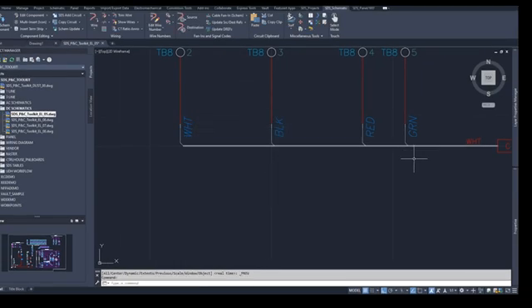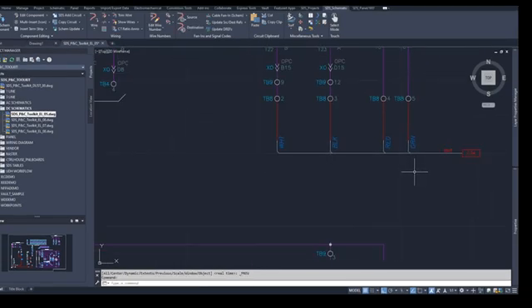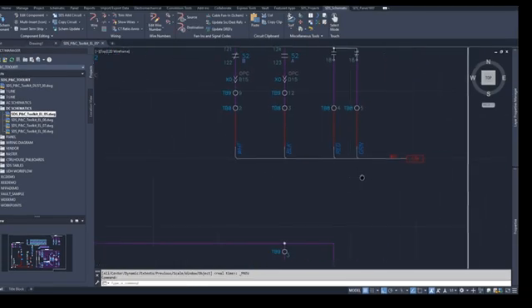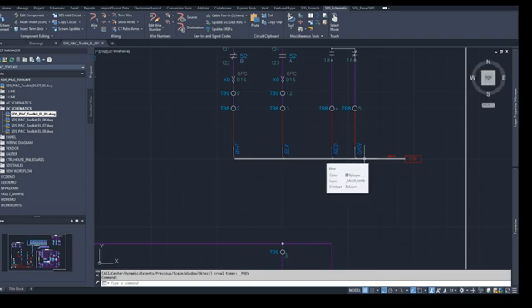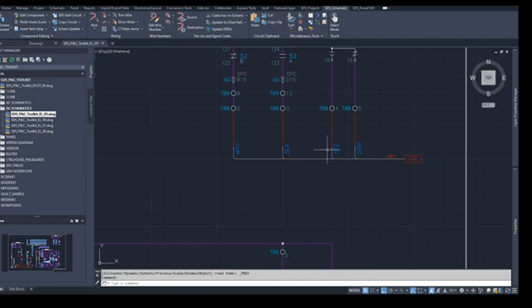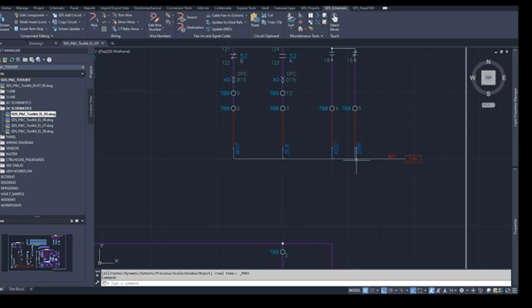Including drawing the wires in using the magical multi-wire layer in AutoCAD Electrical. This provides attachment information so it knows that the wires are all connected together, but it doesn't treat it as an actual wire where you'd have short circuits and so on. But then it does also provide the data saying that C74 is the cable that's attaching all four of these wires.